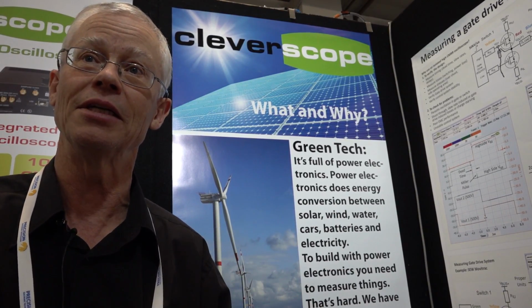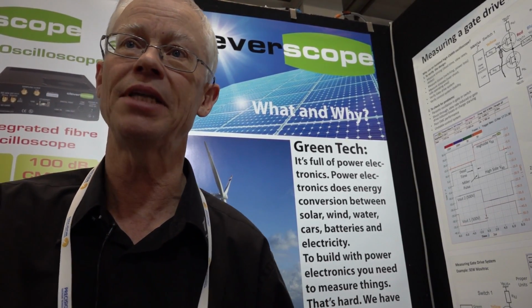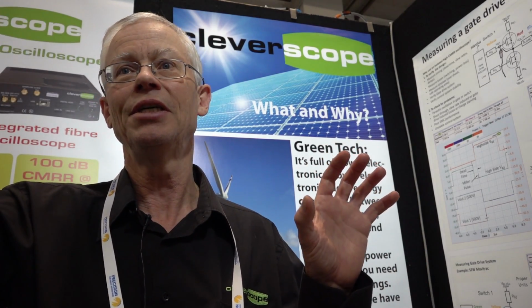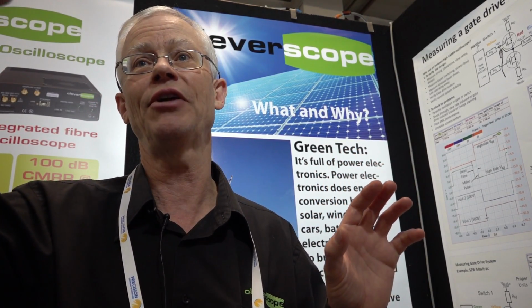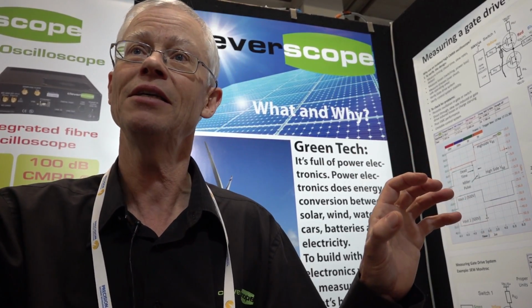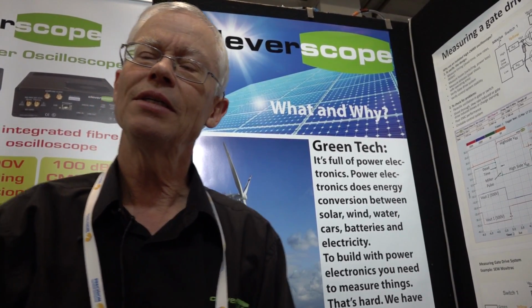Exactly, and in the process of doing that, we also had to change our own front end design. Our front end still works perfectly well with the standard probe, but what we've done is we've matched the characteristic of the Pentec probe with our front end, so they beautifully match across the whole frequency bandwidth, and they give us 1 part in 8,000 linearity. So what did you have to tweak to do that? And why don't they do it on standard? Well, I know why they don't do it on standard probes, because they don't have to. 14-bit converters? No, 8-bit converters. And you've probably got two bits of LSB noise as well. It's only 1 in 100 is all you need. And if I try and do these sorts of tests with my tech scope, I can't even see it.